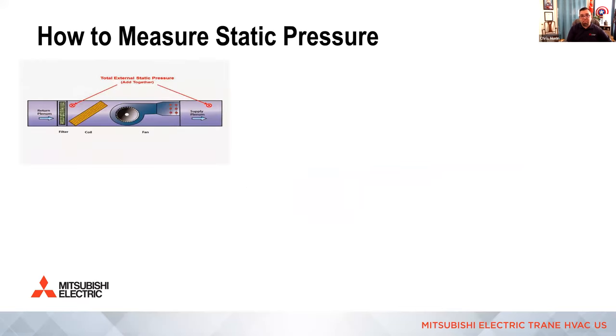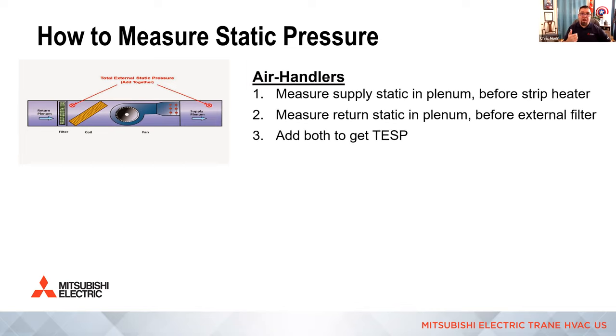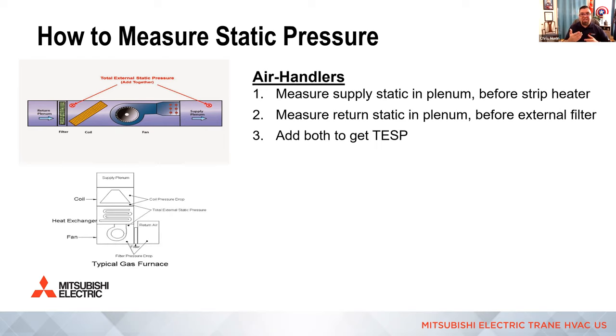So when you're measuring this, you want to measure as close to the box that's shipped with the blower as possible. So it's really easy with, like, a Mitsubishi air handler, right? Because the coil and the blower and everything's all in that box. And if we just use that washable filter that shipped with the unit, we can just put a hole in the supply and return, probably 10 to 12 inches away from each, and measure supply and return static pressure. It's really, really easy.